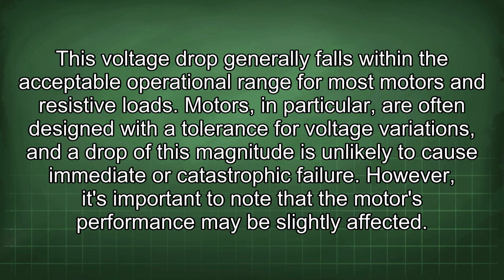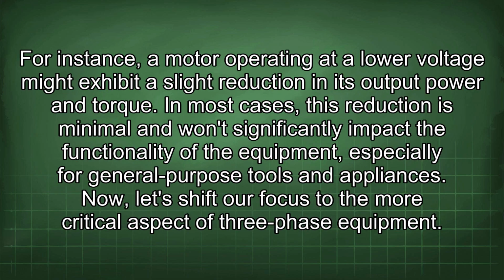However, it's important to note that the motor's performance may be slightly affected. For instance, a motor operating at a lower voltage might exhibit a slight reduction in its output power and torque. In most cases, this reduction is minimal and won't significantly impact the functionality of the equipment, especially for general-purpose tools and appliances. Now let's shift our focus to the more critical aspect of three-phase equipment.